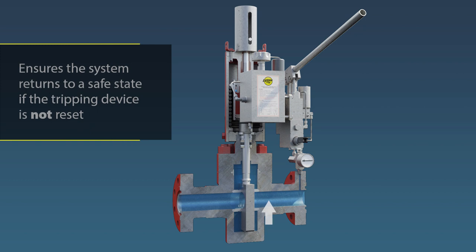The Streamflow self-contained hydraulic system has an added safety feature that ensures the actuator will slowly return to the closed position. This is called the Auto Bleed Down feature, and it prevents the SSV from remaining in an overridden position where the line valve becomes inadvertently locked open.